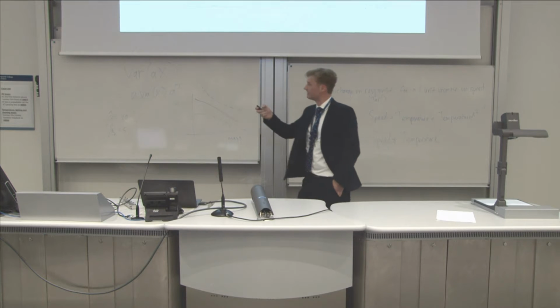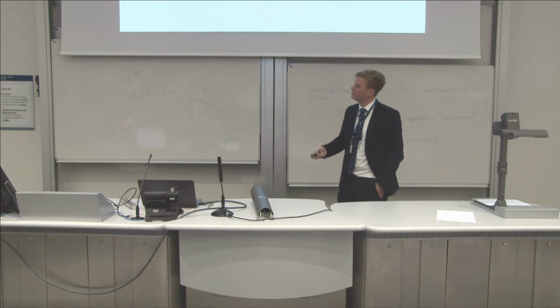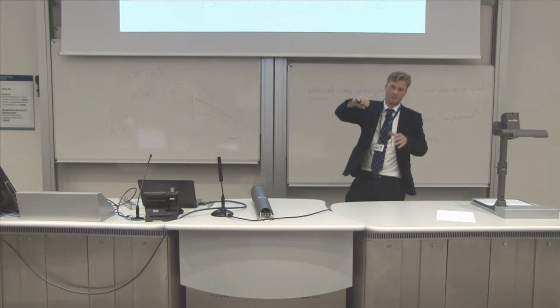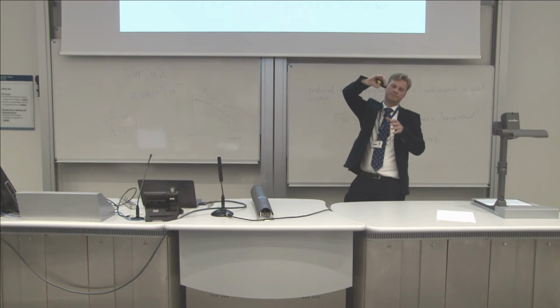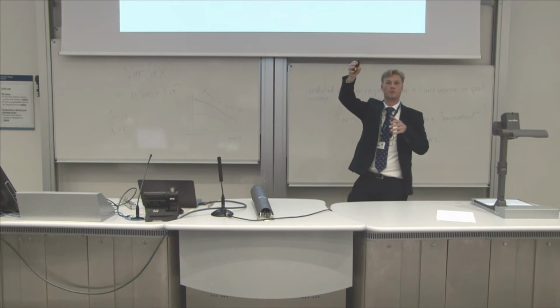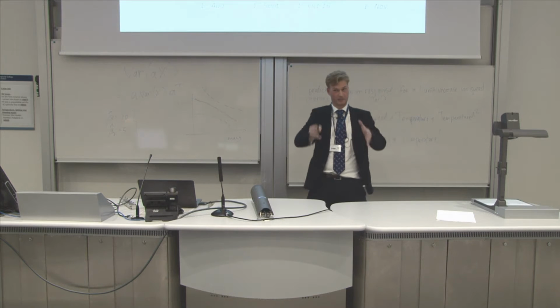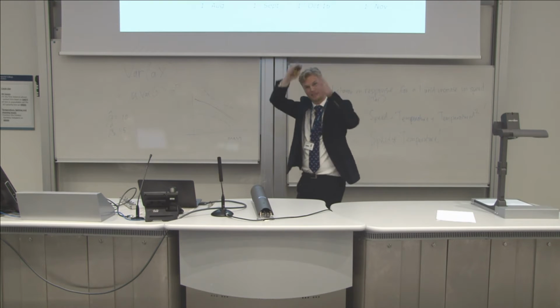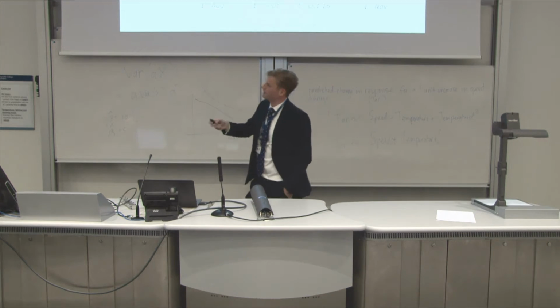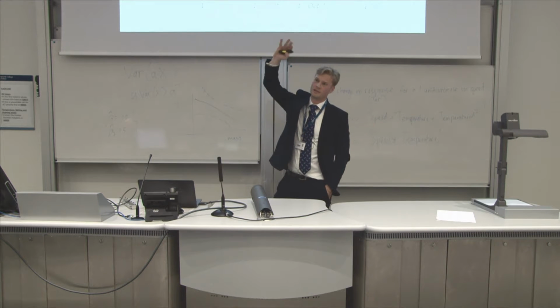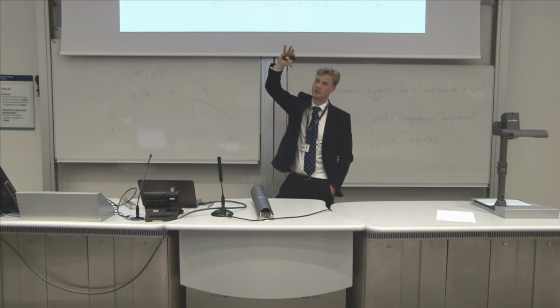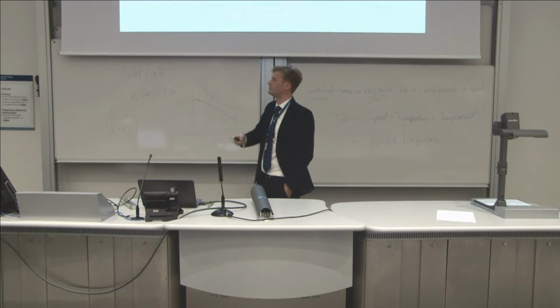This is a real example from a refinery. This is a sensor installed at the overhead pipe coming out of a crude distillation unit, where the distillate comes out. There's a big problem that often there's condensation, and when condensation occurs, some corrosive species fall out, and you get corrosion on the pipe walls.